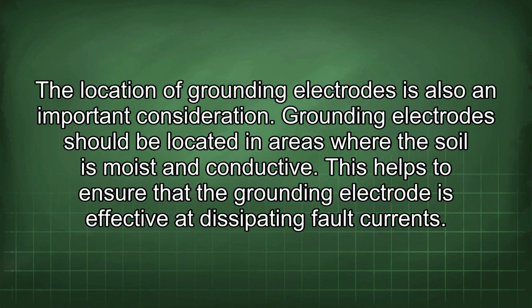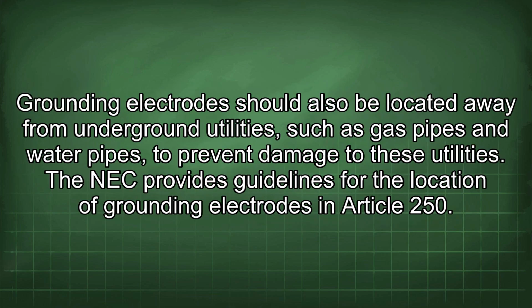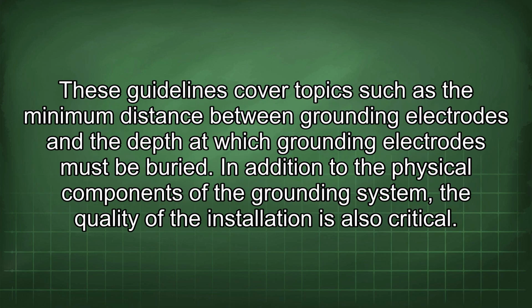The location of grounding electrodes is also an important consideration. Grounding electrodes should be located in areas where the soil is moist and conductive. This helps to ensure that the grounding electrode is effective at dissipating fault currents. Grounding electrodes should also be located away from underground utilities, such as gas pipes and water pipes, to prevent damage to these utilities. The NEC provides guidelines for the location of grounding electrodes in Article 250. These guidelines cover topics such as the minimum distance between grounding electrodes and the depth at which grounding electrodes must be buried.